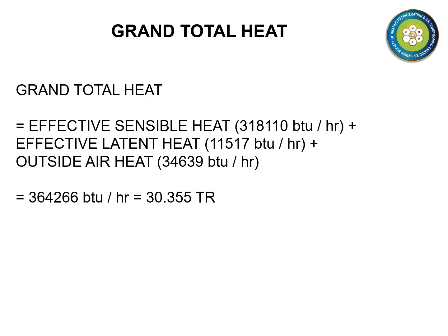On this slide, we have calculated the grand total heat load. It works out to 364,266 BTUs per hour or 30.355 tons.